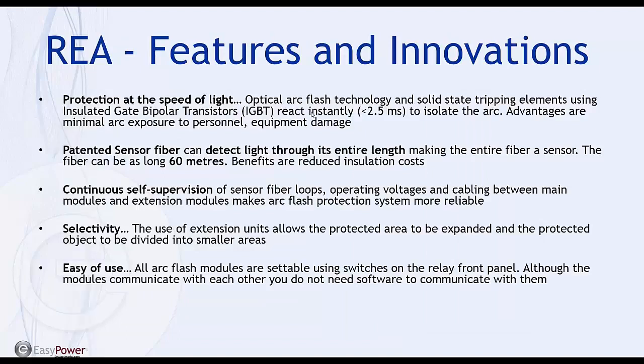The main feature of the REA arc flash system obviously is speed. Now it operates at the speed of light. It's certainly among the fastest out there, if not the fastest out there, less than 2.5 milliseconds. And the solid state tripping elements use insulated gate bipolar transistors. Because it operates so fast, you're protecting personnel and equipment from damage, and that's the main takeaway here. And I challenge anyone to find arc flash systems that can operate faster than that.